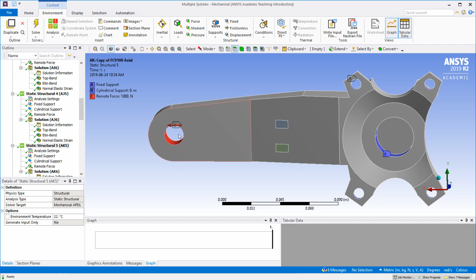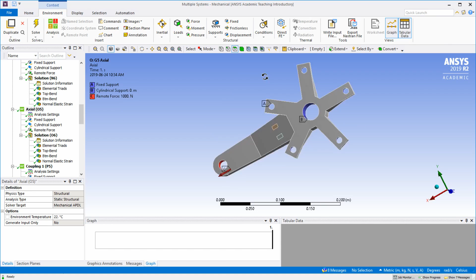All right. When we look at the same simulation with all those gauges moved, about 350 microstrain, 265. So by fixing some of the calibration issues, we've just caused massive axial problems. So you're trading off one against the other. But it doesn't seem to matter that much what we're doing with the 5-arm version that's symmetric.